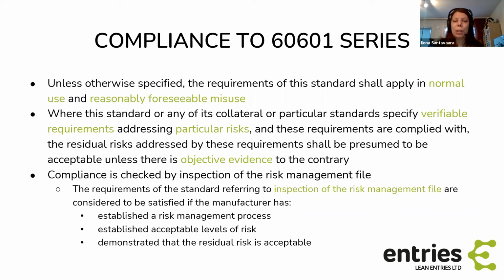You must have established what is an acceptable level of risk. You must have taken everything into account from the standard that needs to be taken into account in risk management, and sometimes how you handle the risk can just be that you are doing design according to 60601. And as was stated, if there's a verifiable means of knowing that it's okay, it can be presumed that the risk is then on an acceptable level. And then you must also demonstrate that residual risk is acceptable.